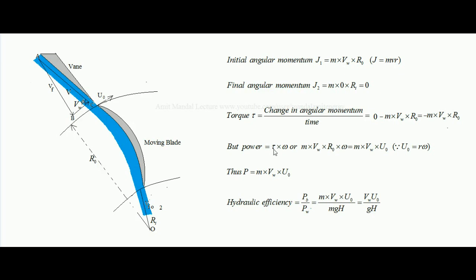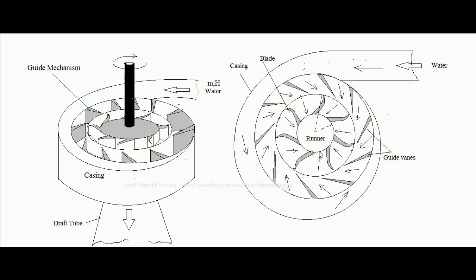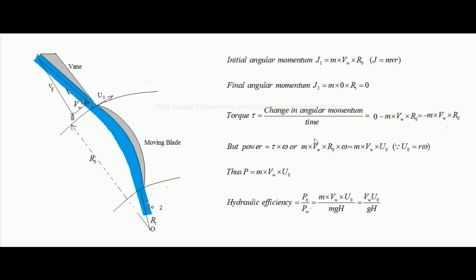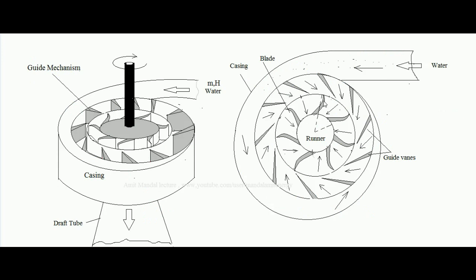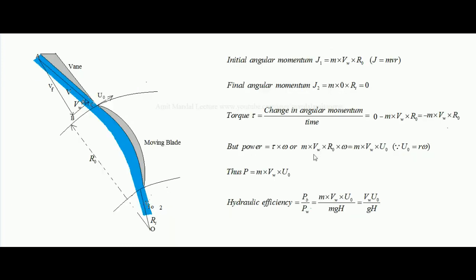In rotational motion, power is given by torque multiplied by angular velocity omega. So power = m·v_w·r_o·omega. Since tangential velocity v = r·omega, we have r_o·omega = u_o, the tangential velocity of the blade tip at inlet. Therefore, the total power developed over the blade is P = m·v_w·u_o, where v_w is the tangential component of water velocity at inlet and u_o is the blade tip tangential velocity at inlet.